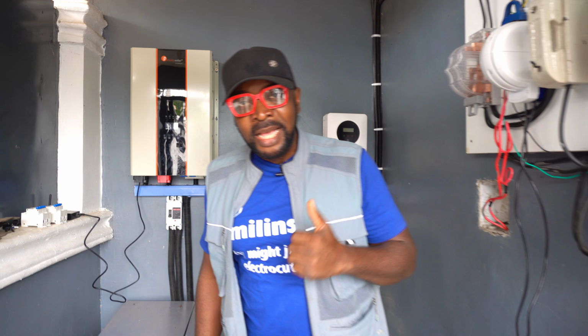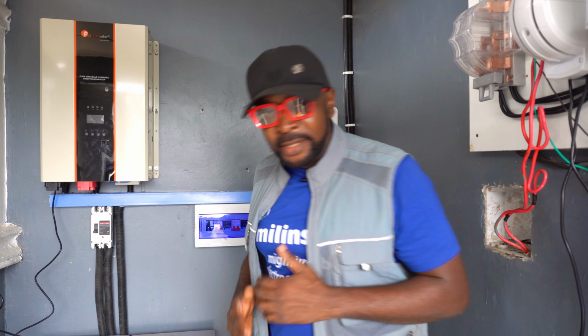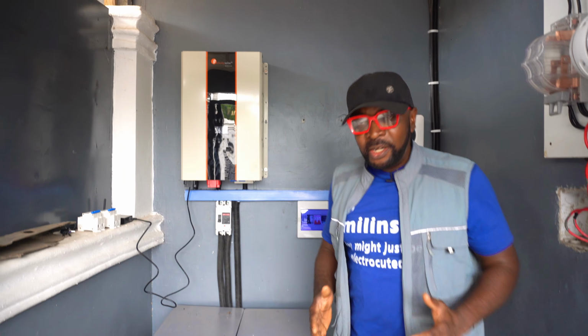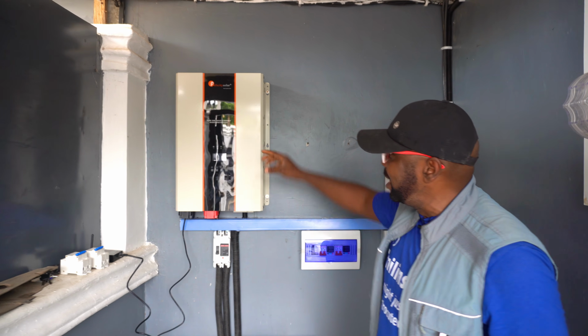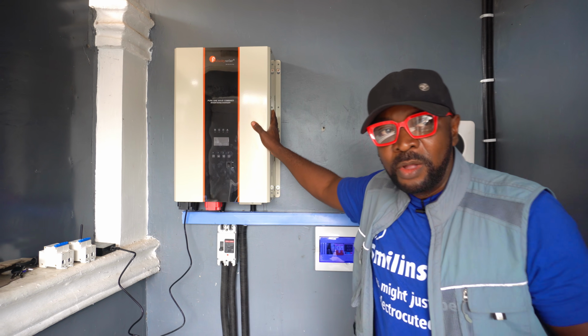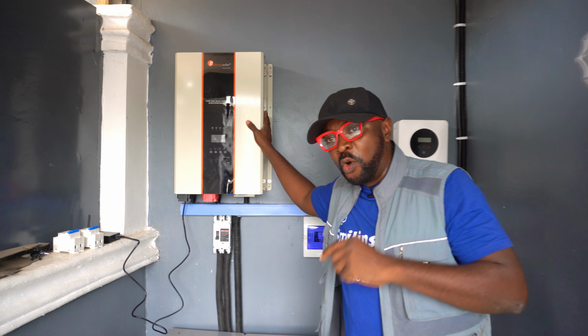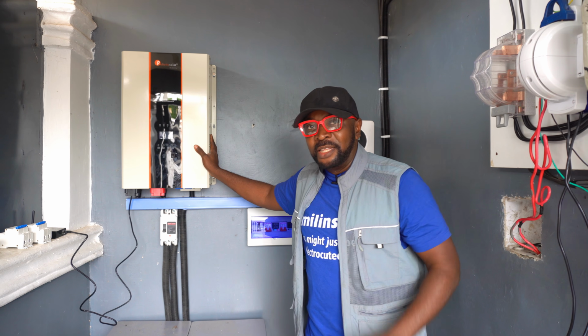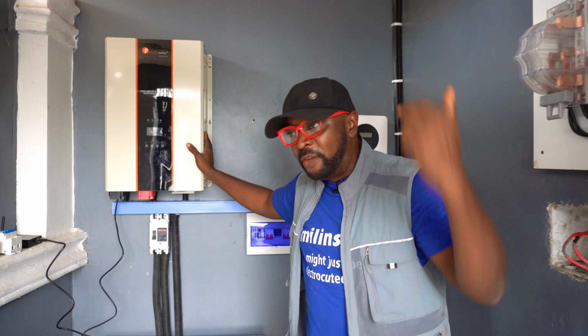It has a heat sensor. When it senses the system heating up, the fan kicks in quickly to bring down the temperature. Once it does that, the fan is expected to go off. But with this particular inverter, the fan keeps running all the time, 24 hours a day.